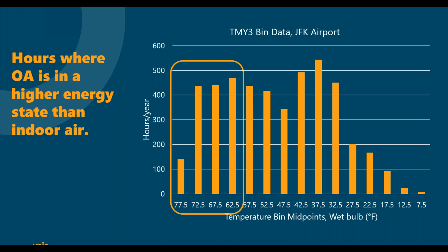So the ventilation energy is significant, and here's just an example of why. This is an example of bin data from ASHRAE Climate Zone 4A. This is bin data that's a typical office operation, so Monday through Friday with some hours on a Saturday, not running 8760. And this is simply illustrating that there are 1,500 hours a year when that outdoor air has a higher energy state than the indoor space set point. So this translates directly into electrical energy needed to meet that sensible and latent load of bringing that air from its outdoor condition down to the space set points. Next slide.